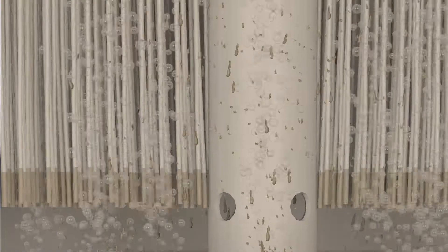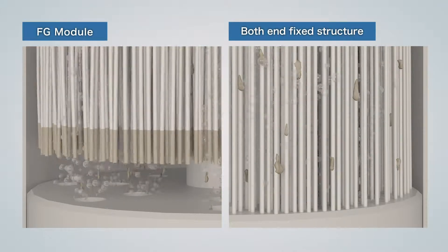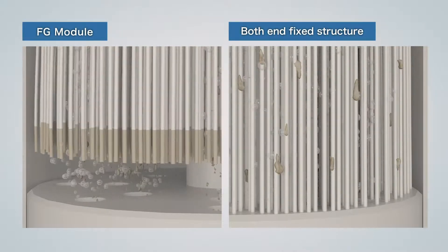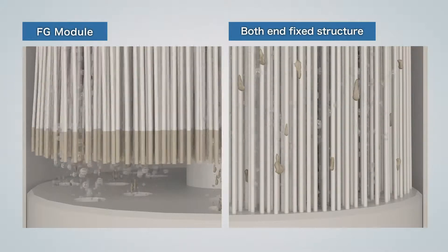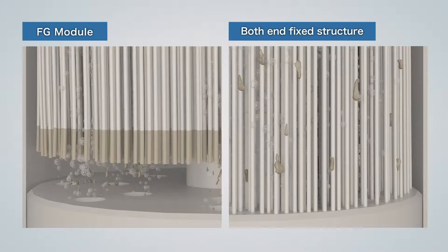The FG module employs a one-end free structure, as the bottom of the hollow fiber membrane is not fixed. Thus, compared to a conventional both-ends fixed structure, the hollow fiber membrane can sway easily, and so the discharge of particles is excellent.